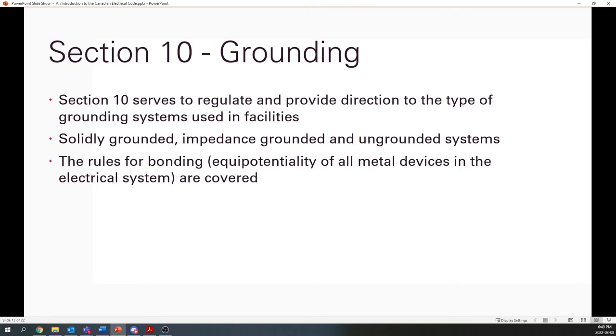This depends on what's called a solidly grounded system, as I said here. I won't talk about impedance grounded or ungrounded systems, they're a bit more confusing, but the majority of systems, for example, the systems in our houses and most commercial installations, are going to be solidly grounded systems where all those electrical parts are connected to ground, so that if a live wire were somehow to touch the metal box, the current would be directed to ground and the circuit breaker would trip. And if those boxes weren't grounded, they would just become live, raised to the potential of whatever voltage that is, and you might get a shock. So section 10 talks about how that actually happens.